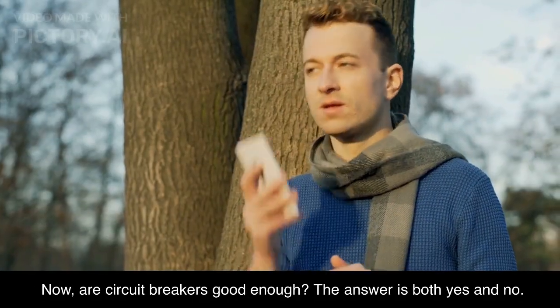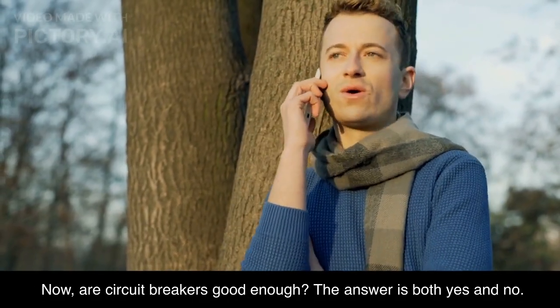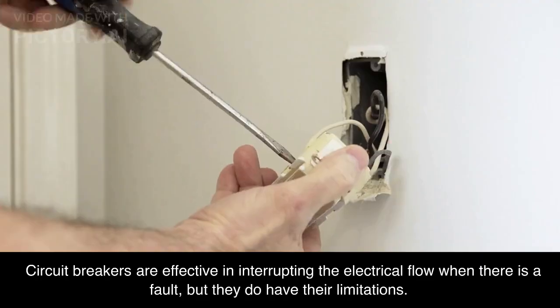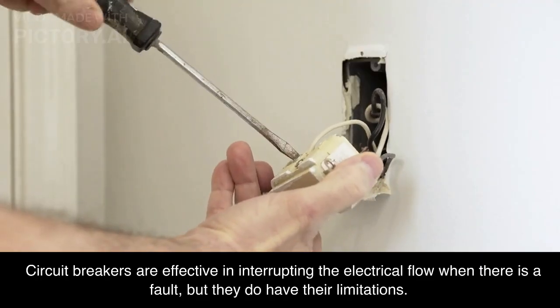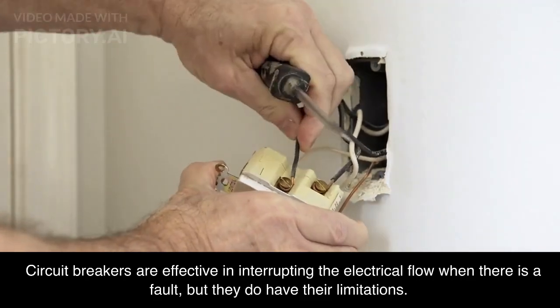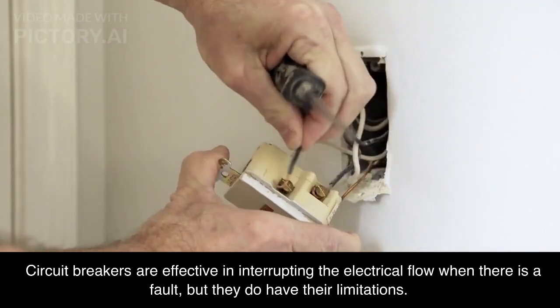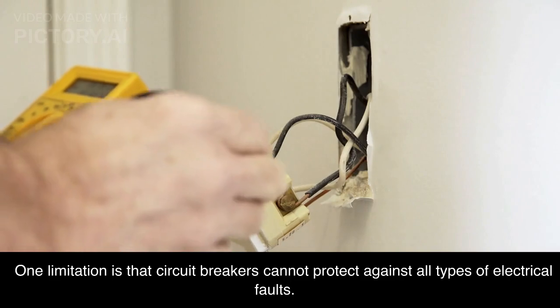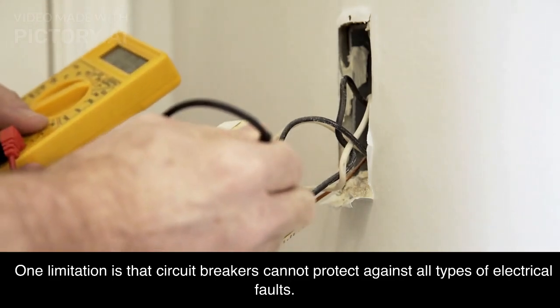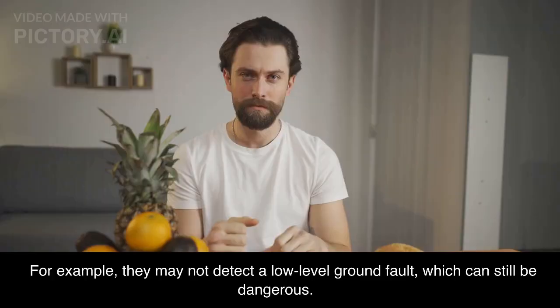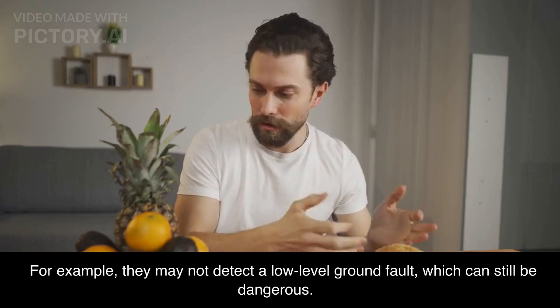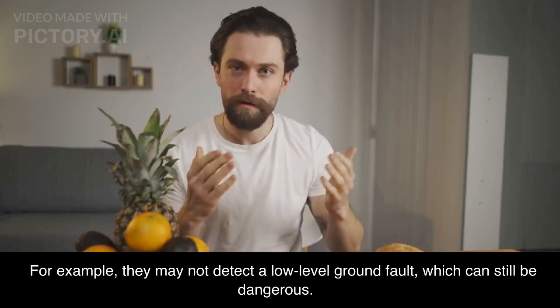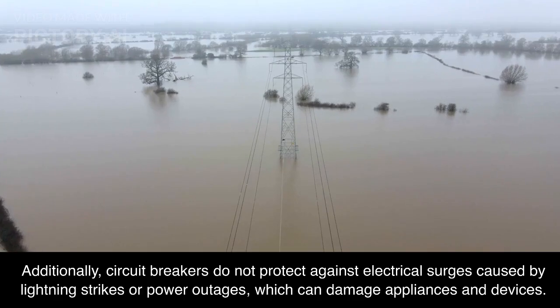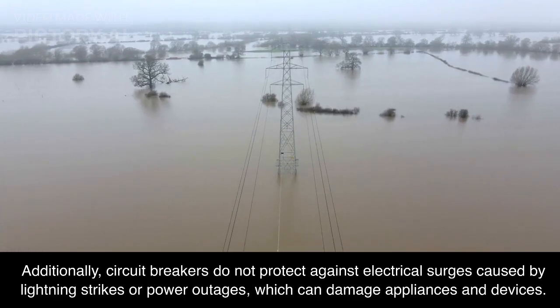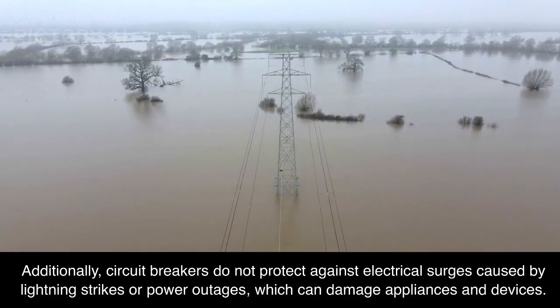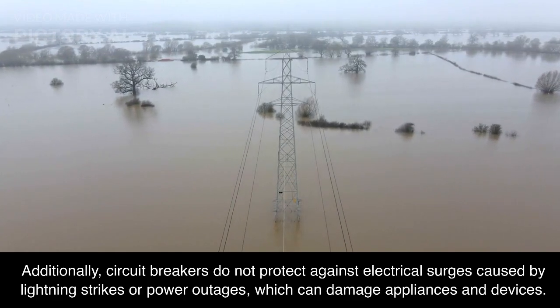Now, are circuit breakers good enough? The answer is both yes and no. Circuit breakers are effective in interrupting the electrical flow when there is a fault, but they do have their limitations. One limitation is that circuit breakers cannot protect against all types of electrical faults. For example, they may not detect a low-level ground fault, which can still be dangerous. Additionally, circuit breakers do not protect against electrical surges caused by lightning strikes or power outages, which can damage appliances and devices.